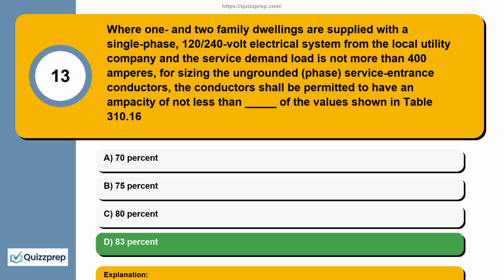Section 310.12(A) allows the service entrance conductors to have an ampacity not less than 83% of the service rating.